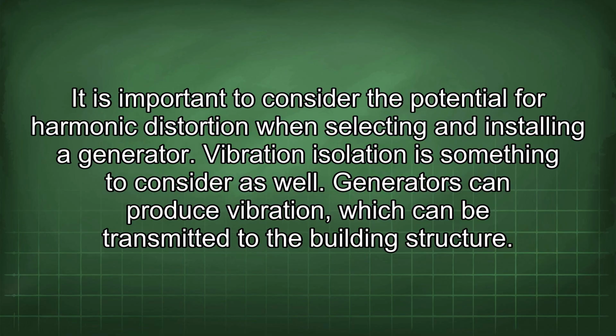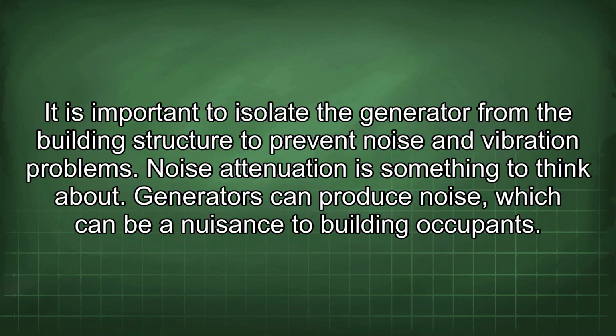Vibration isolation is something to consider as well. Generators can produce vibration, which can be transmitted to the building structure. It is important to isolate the generator from the building structure to prevent noise and vibration problems.